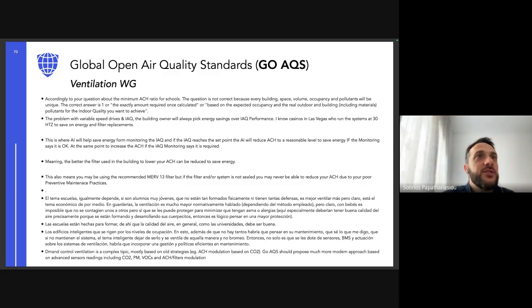This is where AI can help save energy while monitoring indoor air quality - if the indoor air quality reaches the set point, the AI reduces air exchange rates to a reasonable level to save energy, and increases it again if monitoring shows it's required. It also means you may be using recommended MERV 13 filters, but if the filter or system isn't sealed, you may never be able to reduce your air exchange rates due to poor preventive maintenance practices. Demand control ventilation is a complex topic, mostly due to old strategies - a good indoor air quality system should propose a more modern approach based on advanced sensor readings, including CO2, PM, VOCs, and filtration modulation.